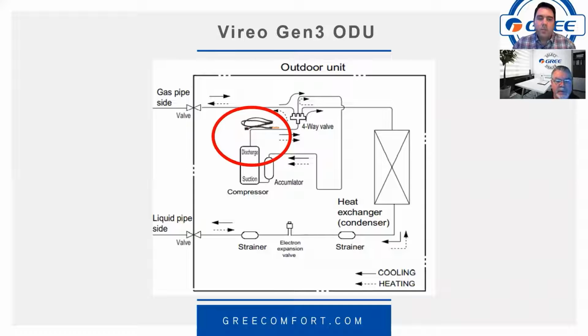So on this Vireo Gen 3, one of the potential causes, people will talk about a high pressure switch. Not all systems have high pressure switches. In fact, all of the mini split series have just a temperature sensor, discharge temperature sensor, and the 18,000 BTU multi-zone also has just a discharge temperature sensor. So it's actually a pressure reading or a temperature reading being converted to a resistance value that the main board is going to do calculations to determine whether or not to initiate that E1.